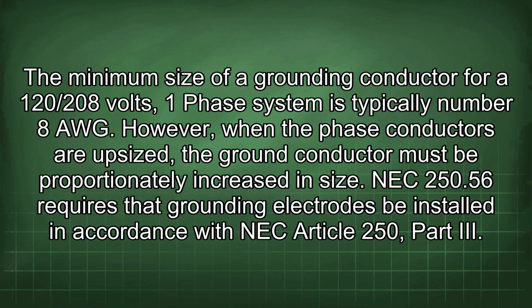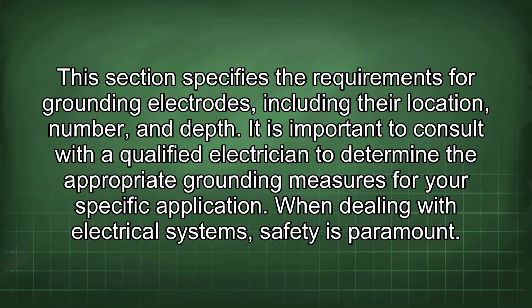The minimum size of a grounding conductor for a 120/208 volts, one-phase system is typically number 8 AWG. However, when the phase conductors are upsized, the ground conductor must be proportionately increased in size. NEC 250.56 requires that grounding electrodes be installed in accordance with NEC Article 250, Part III. This section specifies the requirements for grounding electrodes, including their location, number, and depth. It is important to consult with a qualified electrician to determine the appropriate grounding measures for your specific application.